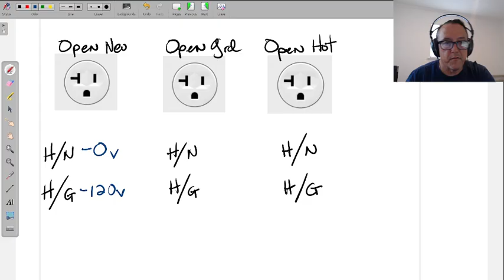But so we want to know, what does that mean? If the lamp isn't working, what does it mean by no power? So let's do first open neutral. So open neutral is going to have 120 volts between the hot and the ground, but it's going to give you 0 volts between the hot and the neutral. So if you, for example, head over to this outlet to check because the lamp wasn't working, and you put your meter on one side, the bigger side is always the neutral, and then you put it over here, and your meter says 0, and you're like, well, there's no voltage at the outlet.